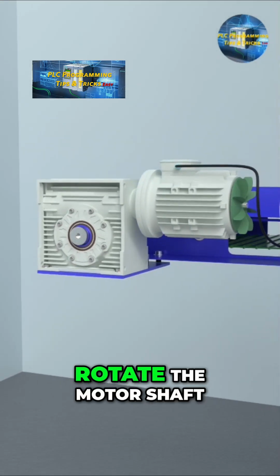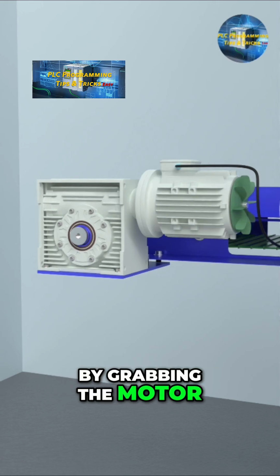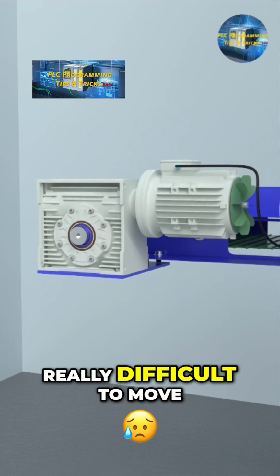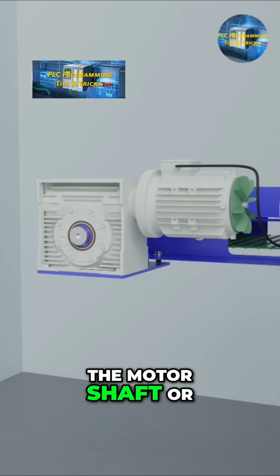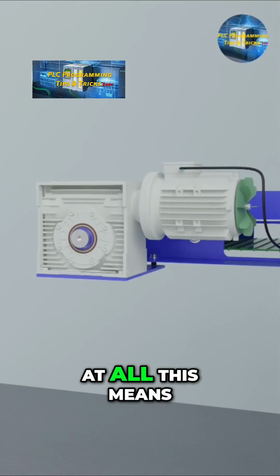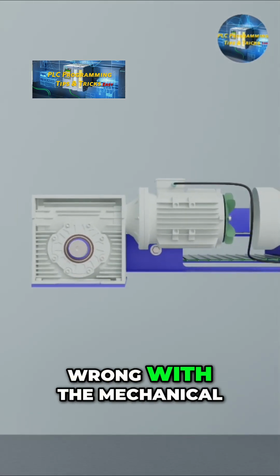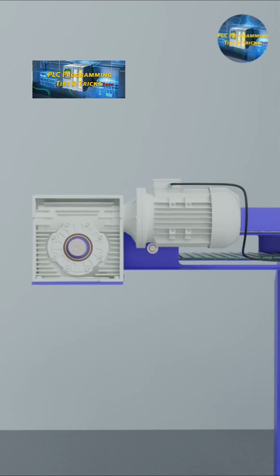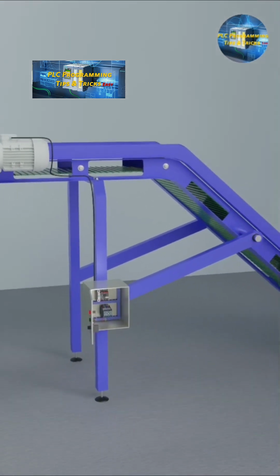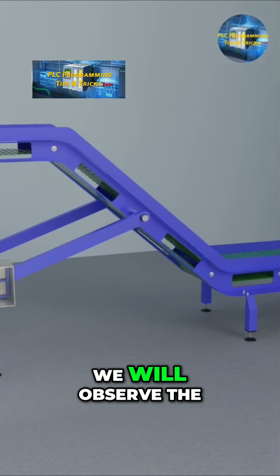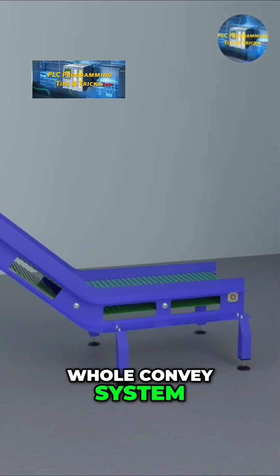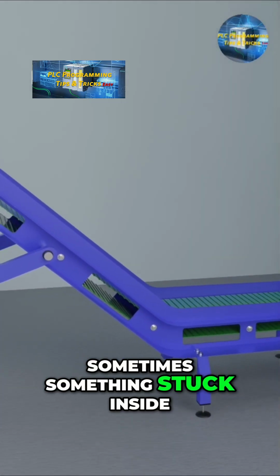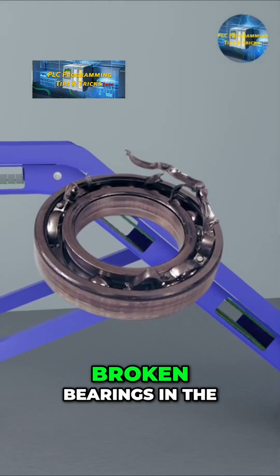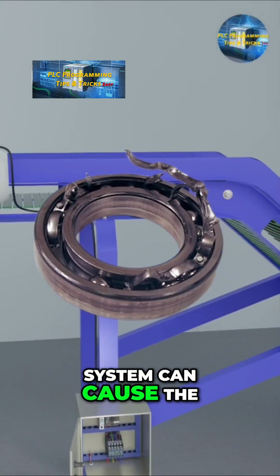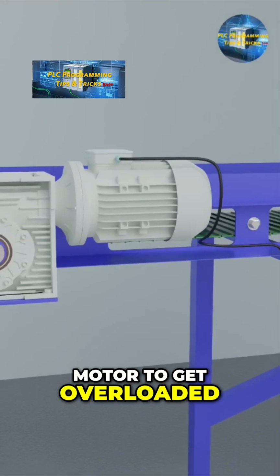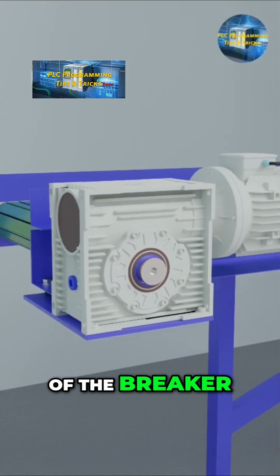If you try to rotate the motor shaft by grabbing the motor fan and you find it really difficult to move the motor shaft, or it is not moving at all, this means that there is something wrong with the mechanical components of the system. So first of all, we will observe the whole conveyor system. Sometimes something stuck inside the conveyor belt or broken bearings in the system can cause the motor to get overloaded and cause the tripping of the breaker.